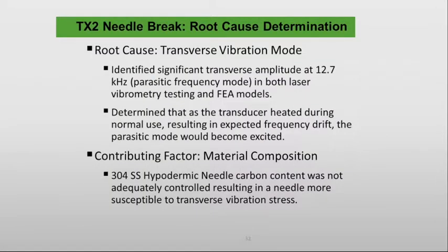So the physics of the problem was very interesting. It showed that as we made the probe longer, we got into a significant and somewhat unanticipated transverse or side-to-side vibration mode. And so the strain that was being applied to the probe as it inserts into the handpiece was extreme. And it was extreme enough to exceed the material properties of the probe. And so this was playing into the failure mode. So there are ways to adjust the manufacturing to dampen the side-to-side amplitude, and that was done.